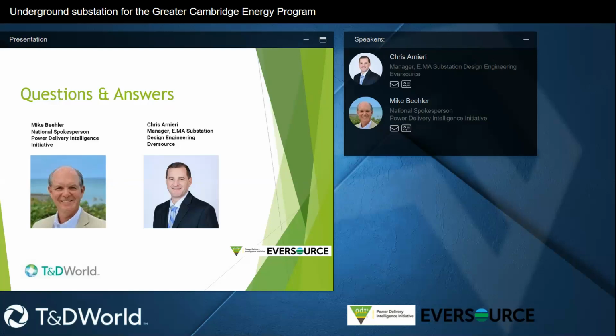So here's the last question, and it's actually the one I want to talk about: cost. What's the cost difference between the underground substation versus a comparable air-insulated switching station above ground? This one's a little tough, because if you try to compare it to a traditional air station, you really have to match technology for technology. Typically, going from air insulated to gas insulated substation involves a very big cost delta.